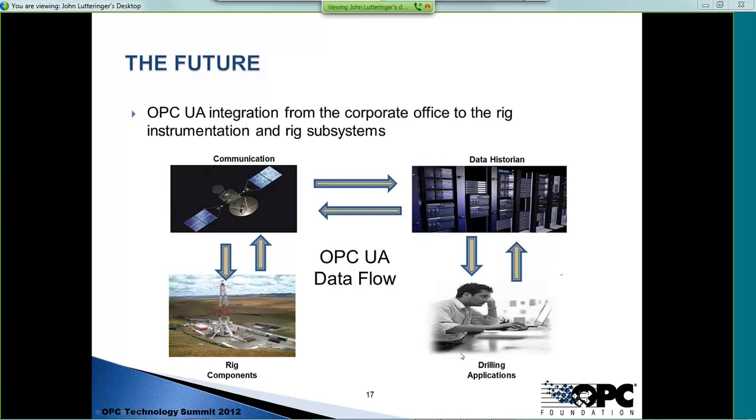So where we're using InduSoft is here at the rig location, for one place. Today we take that serial feed coming from the MD Totco or the Pason. We convert that into an OPC server and instantiate an InduSoft OPC server to provide data collection there at the rig.